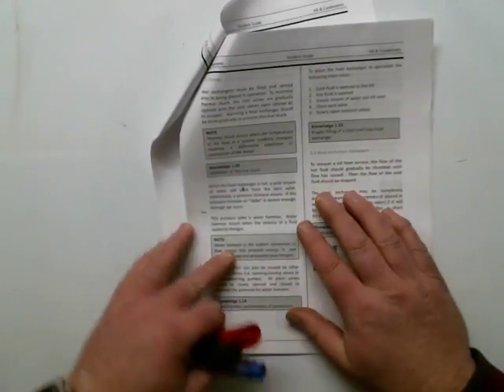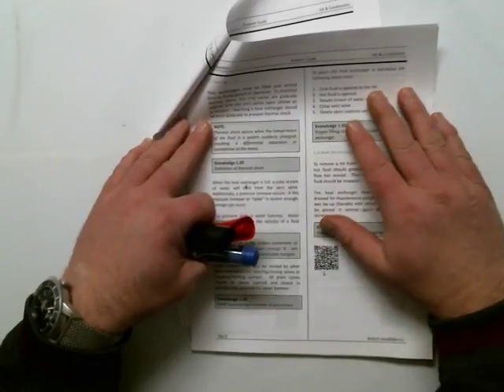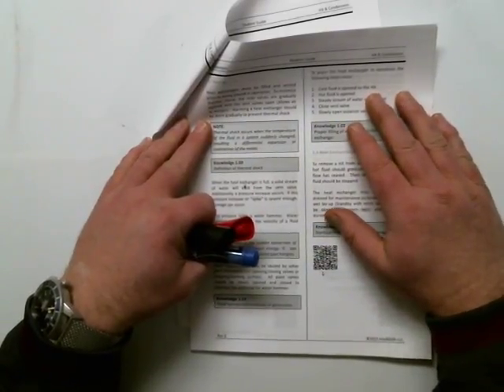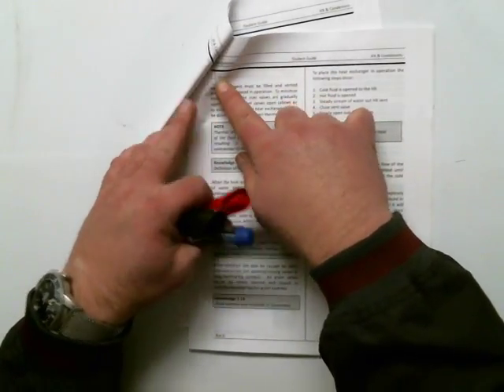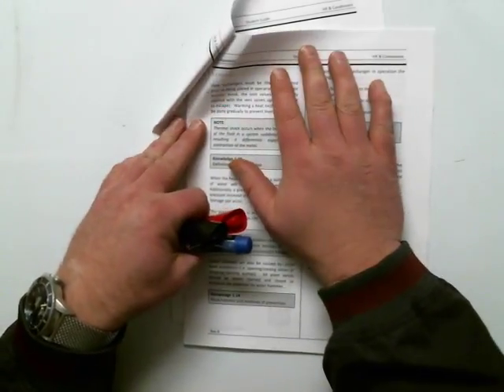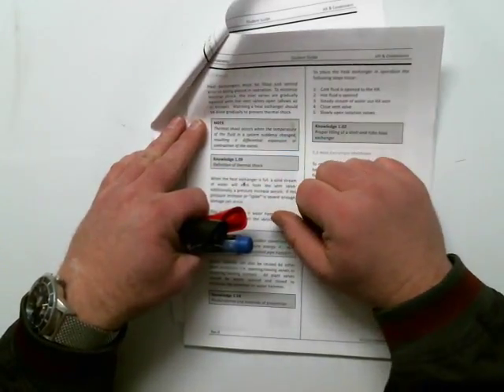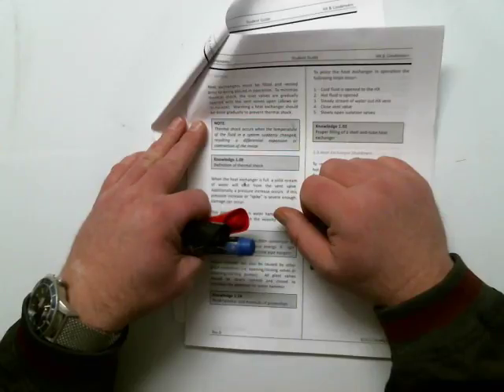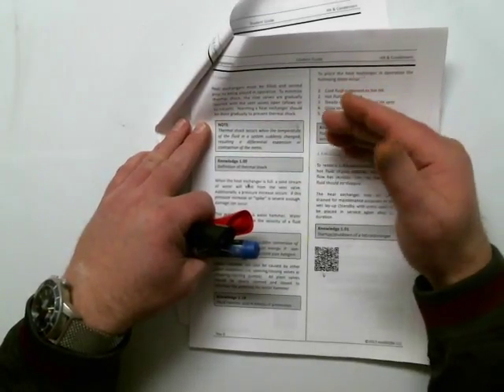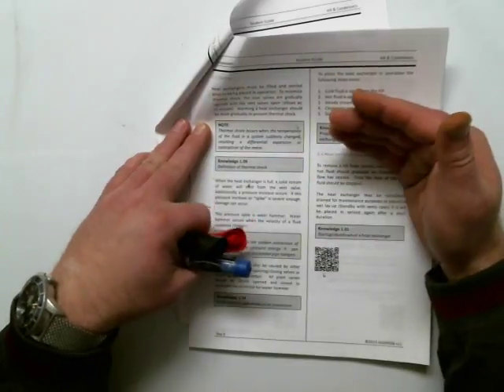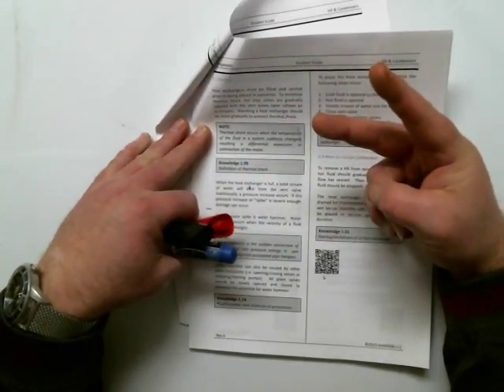One of the things that's important is how to start up a heat exchanger, how to put it in service. So first of all, if you notice, I'm sitting here on section 2.2 startup, and I need to fill and vent the heat exchanger prior to placing it in operation. So when I go to do that, one of the things I want to do is minimize thermal shock. Those are two things that are important.